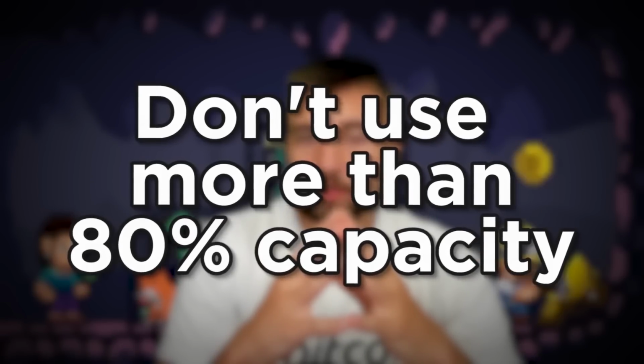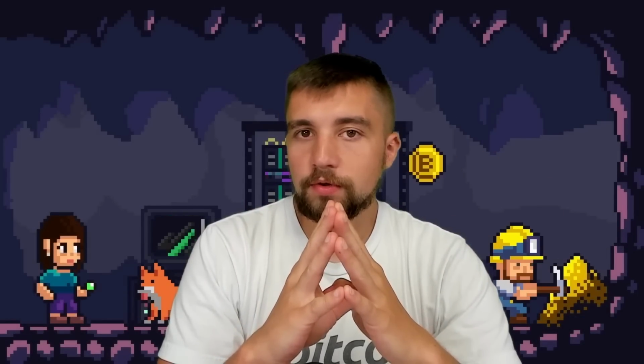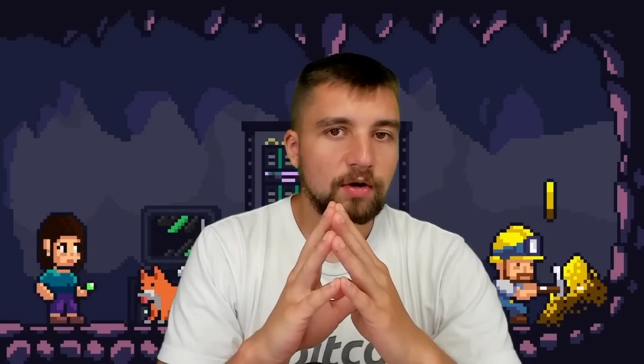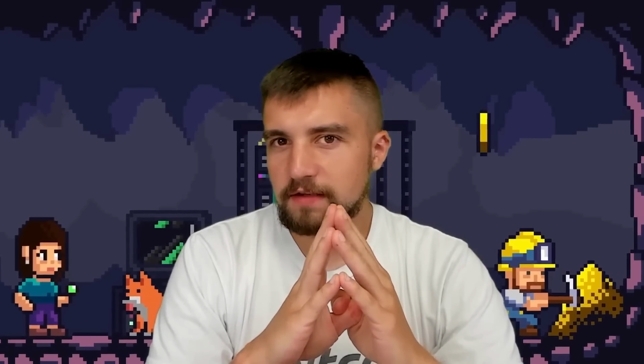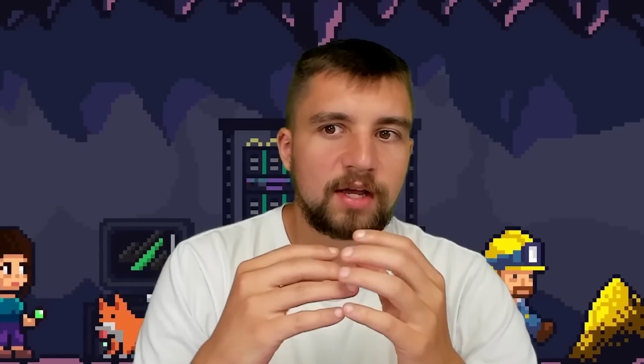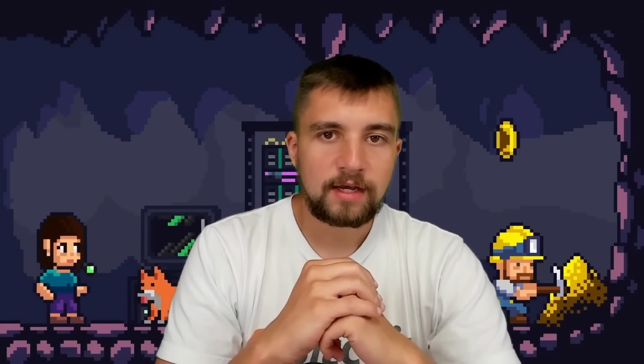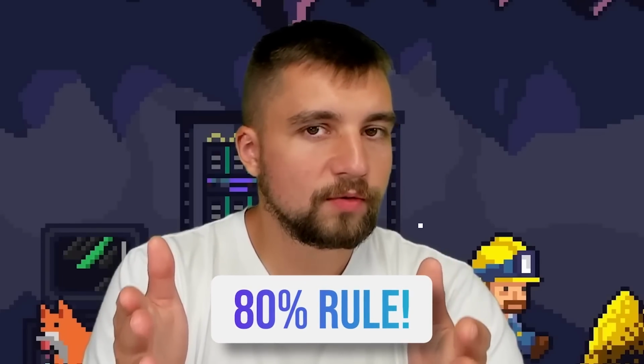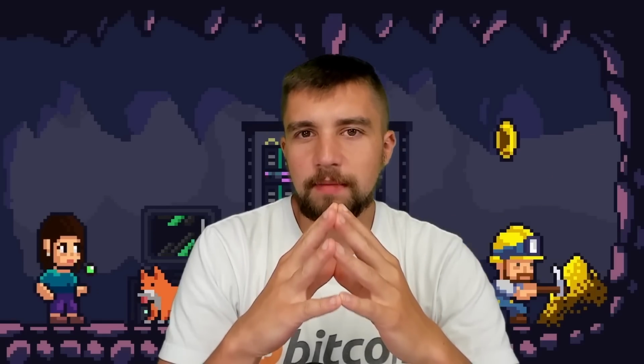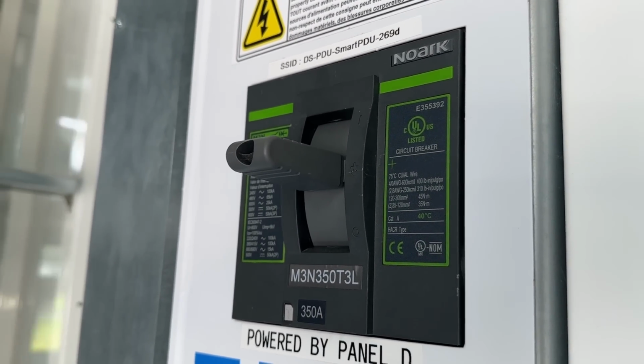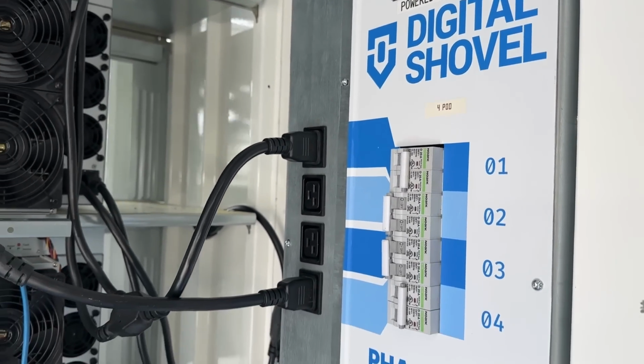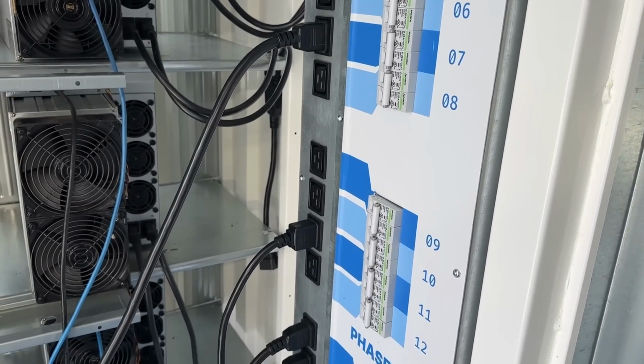You never want to use more than 80% - on a 30 amp outlet you could pull 30 amps, but you shouldn't. Maxing it out starts to become unsafe, and what you're really worried about is exceeding the draw, getting too hot, fire hazard, stuff like that. So if you had 100 amps available, you'd only use 80 amps, especially because mining rigs draw that power 24/7, 365 - they never stop. Understand that electricity being used, consumed, and moved generates heat.